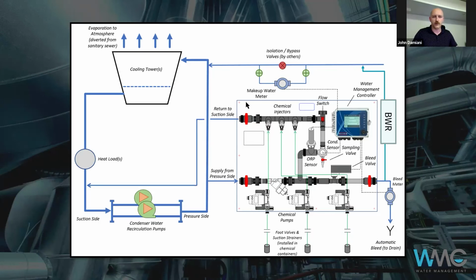I feel like there's not enough importance assigned in the industry to bringing the water treatment guys, whether third party or your existing vendor, on site when your chillers are opened up for inspection—before they're punched, before they're cleaned. That's the report card. When you open that up, that's how you're doing.